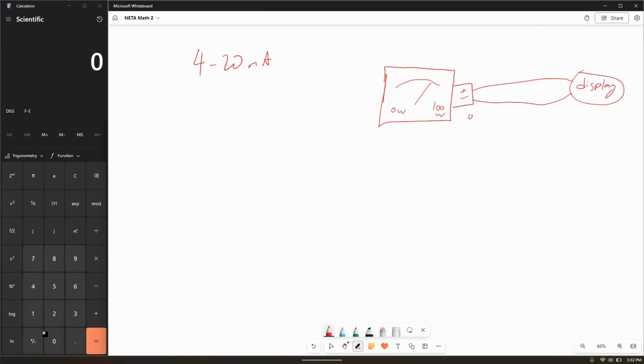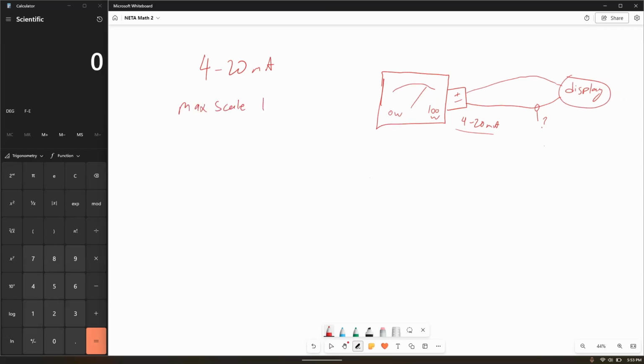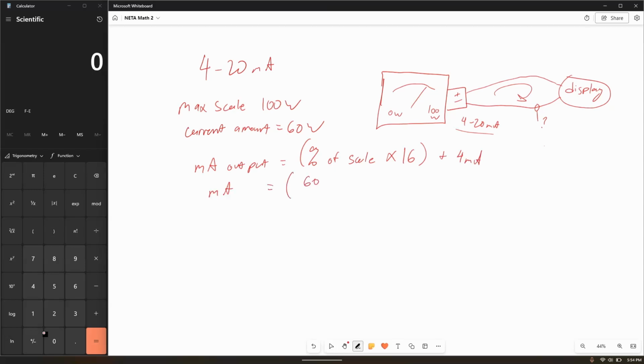So I know that this is supposed to have a 4 to 20 milliamp scale. It has some deadband. If it's below 4 milliamps, the display goes into error. Between 4 and 20 milliamps, it'll display the amount. And if it's above 20 milliamps, you've got something wired wrong, and your display, again, is going to show you an angry error sign. So how do I know how much current should be here through the secondary transducer circuit? If I say the max of this scale is 100 watts, and my current amount is 60 watts, how much current is going to be going through our 4 to 20 milliamp loop right now when we're at 60 watts? So the way that you would solve this sort of thing, our milliamp output equals the percentage of the scale times 16. 16 is the difference between 4 and 20, times 16 plus 4 milliamps, because that's the bottom end of our deadband. So our percentage, we're currently at 60 watts over 100 watts.